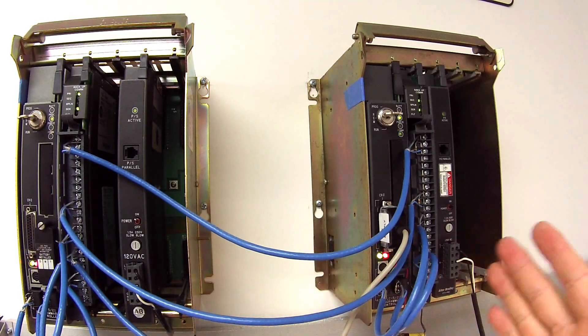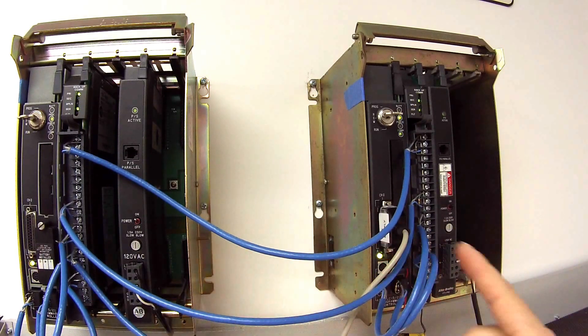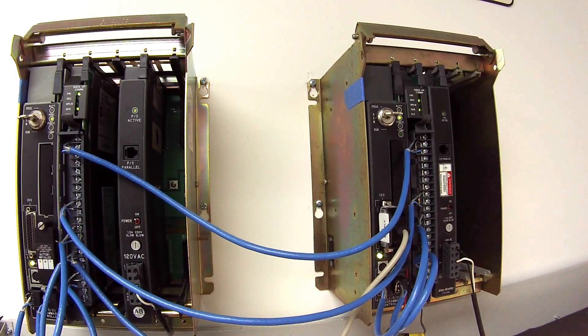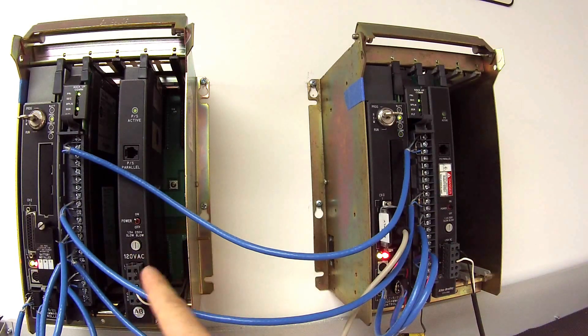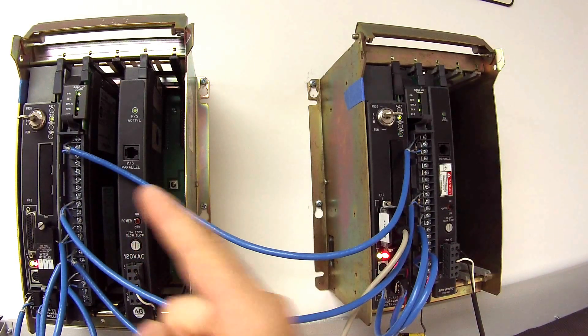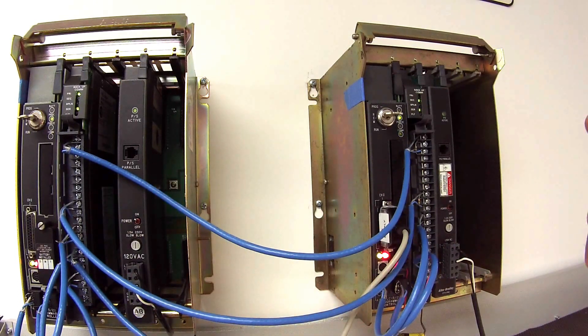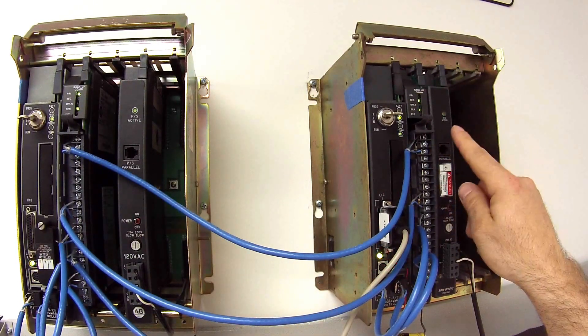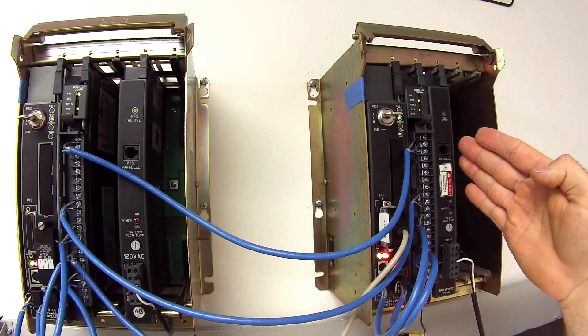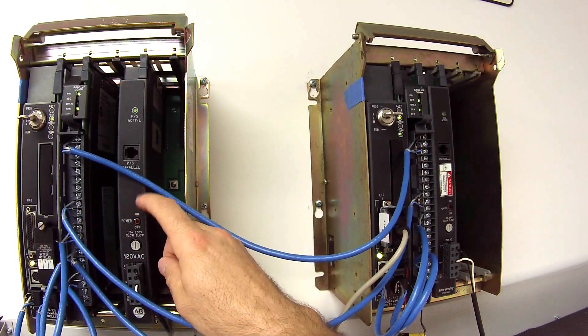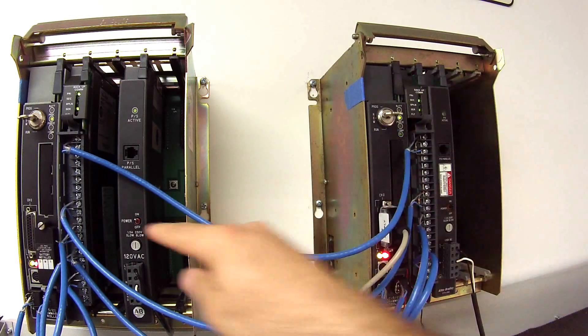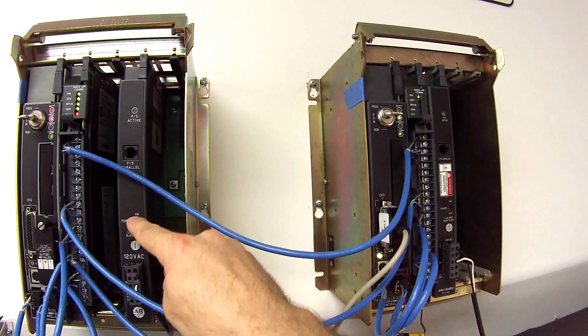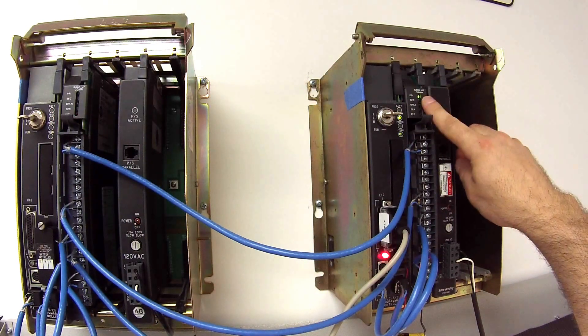So, now that the system is up and running, and it is in remote run mode for this test procedure, I want to simulate a power failure on my primary rack. Now, that's important. It must be on the primary rack to make sure that the secondary rack moves itself into primary and knows what to do and when to do it. I'm going to do that by shutting the power off, so please follow. This light here should move to primary when I shut this off, and it has. That's exactly what I want to see.